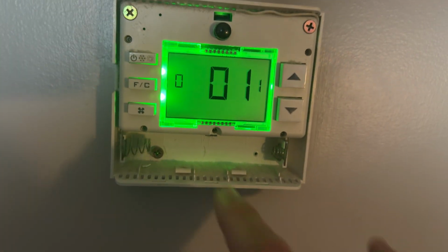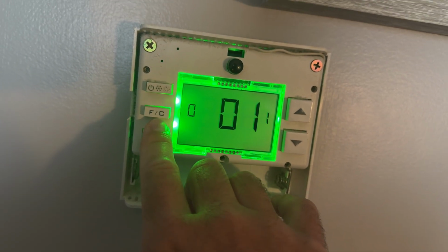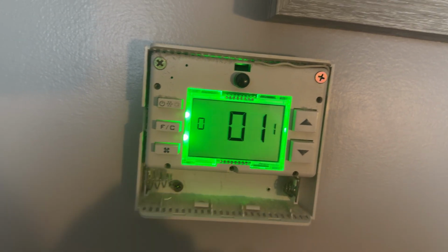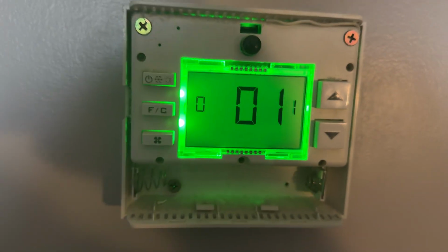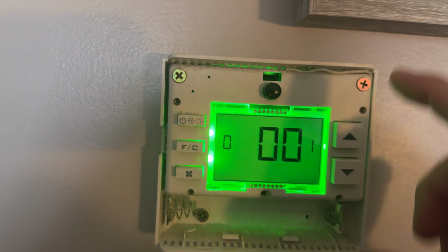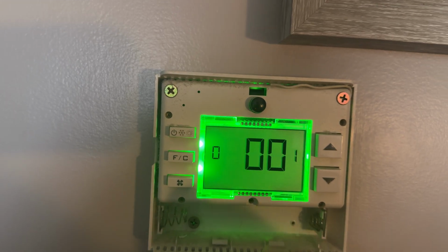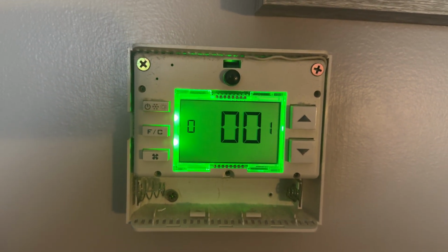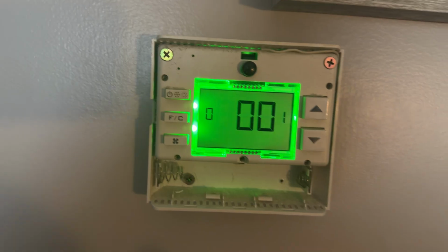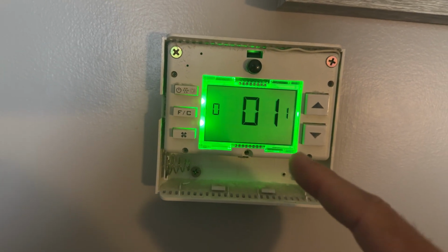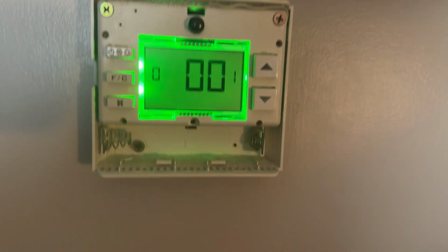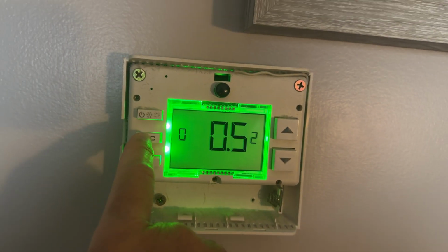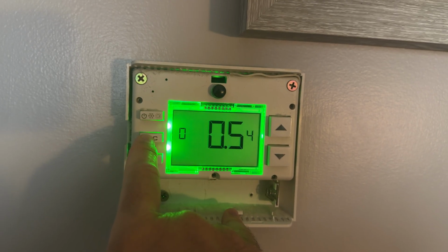And you'll go to the next, let's see, this one right now, you heard the compressor fan shut off. So what you want here is 0, because that makes it manual. And manual says if you want the fan on, you got it on. If you have it on 1, then that automatically shuts the fan off or on, depending upon if the air compressor is running. So you got 0 right there. That's what you want. And you go forward in the menu. Don't worry about these.